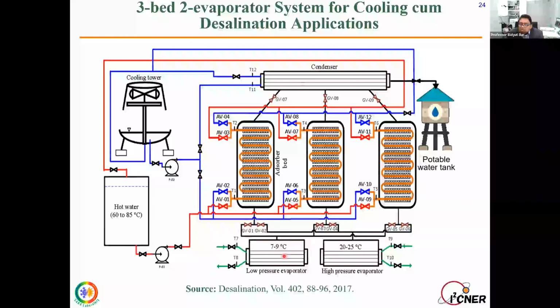And as I mentioned here, water vapor goes in this bed, is adsorbed, then desorbed from this bed, and the moisture comes to the condenser. We use the cooling water to cool down the condensate, and it comes back to our evaporator so that we can get our cooling energy. But here, instead of getting our refrigerant cooled back to the evaporator, we are having this water. When it is cooled down, we store it in a potable water tank, and this is as good as distilled water, the water we are getting, and we are charging our water continuously, like seawater, in these evaporators.